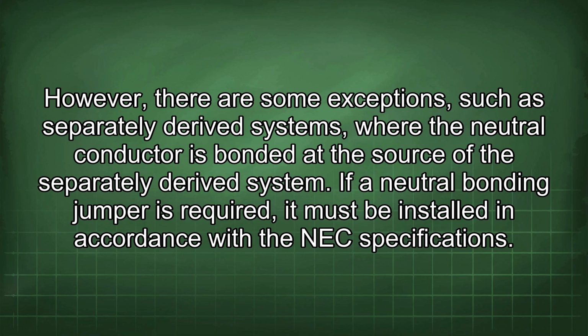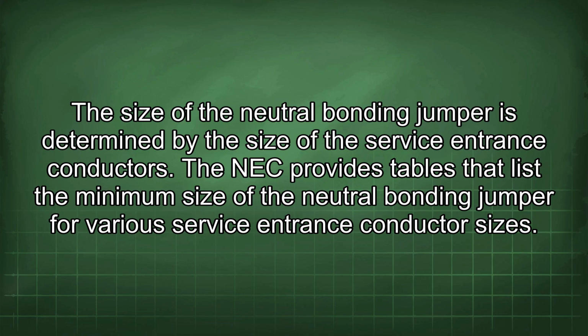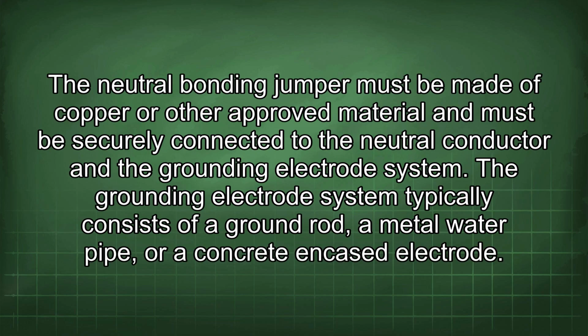If a neutral bonding jumper is required, it must be installed in accordance with the NEC specifications. The size of the neutral bonding jumper is determined by the size of the service entrance conductors. The NEC provides tables that list the minimum size of the neutral bonding jumper for various service entrance conductor sizes. The neutral bonding jumper must be made of copper or other approved material and must be securely connected to the neutral conductor and the grounding electrode system. The grounding electrode system typically consists of a ground rod, a metal water pipe, or a concrete encased electrode.